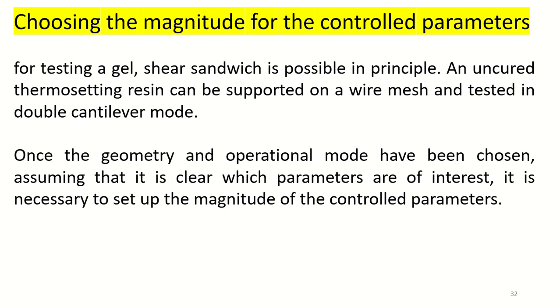For example, for testing a gel, shear sandwich is possible in principle. An uncured thermosetting resin can be supported on a wire mesh and tested in double cantilever mode. A very stiff metal bar is not appropriate for testing in tensile mode because the force needed to deform it is higher than the maximum force allowed by the instrument. On the other hand, a very thin wire made of the same metal can be tested in tensile mode.